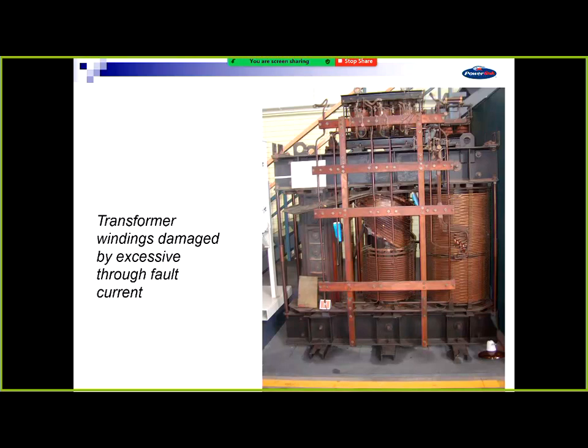This was a fault in there, but actually no, it wasn't. It's an external fault. That's just what I was going to say. You can have external faults which put a lot of forces on the transformer, so they've got to be designed for that level. If you go above that fault level externally, so the fault isn't in the transformer itself, it's actually mechanical damage. And that's another thing with fault current, it might not be an electrical fault, it could be a mechanical fault. You've got structures or fittings which can only handle a certain fault level, and the higher fault level puts more stress on them, and they fail mechanically, not electrically. So that's what's happened on that one there.